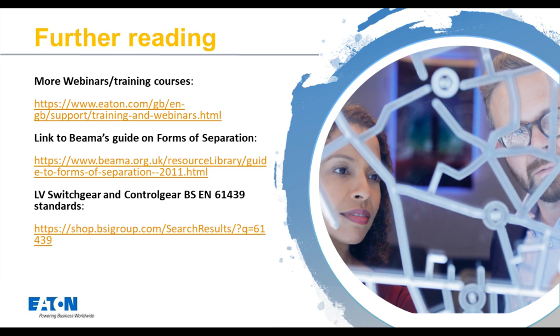As we spoke about during Tariq's part of the presentation about forms of separation, there's a BEAMA guide, which is the British Electrotechnical and Allied Manufacturers Association. This is made up from independent experts from multiple manufacturers, not only Eaton, but people like Schneider, Hager, ABB, smaller panel builders as well. And obviously there's a wealth of information on the BEAMA website, which is all freely downloadable. So there's things like ingress protection, arc fault detection, RCDs, power factor correction, circuit breakers, surge protection devices, a guide to verification, to name a few.